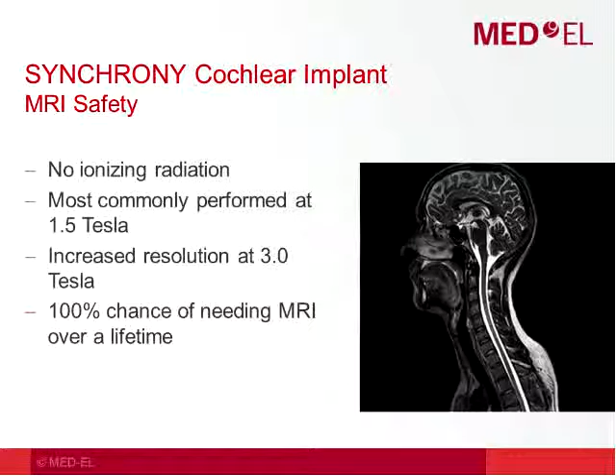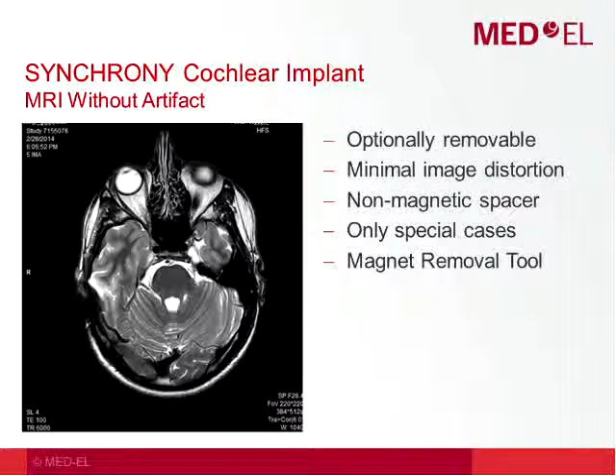So I've also mentioned that this new internal magnet design we have in the SYNCHRONY Cochlear Implant can be removed, and that has to do with the potential for distortion in an MRI. So a magnet inside the head creates a little bit of distortion in the image, so it may be necessary to remove that internal magnet if the doctor needs to scan the head right around the area of the implant. So if this is necessary, MED-EL would of course provide the doctor with any support that they need, and we would also provide special tools to remove the magnet and a spacer that would go in place of the magnet if needed.